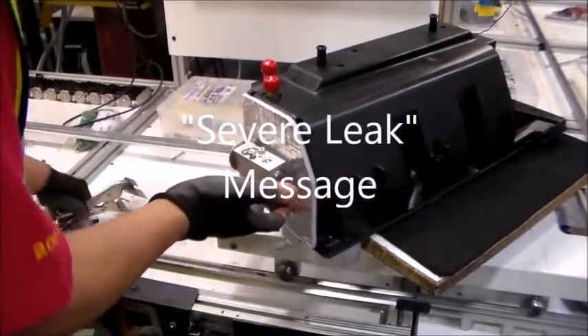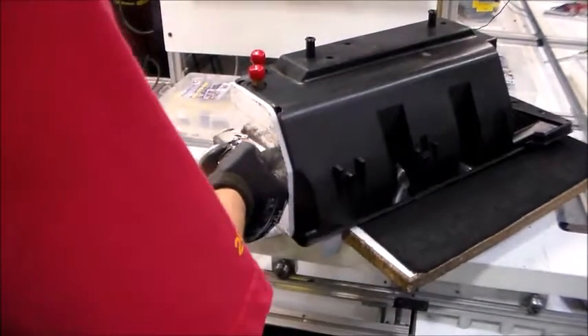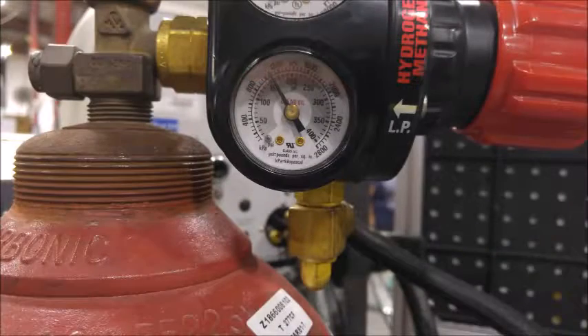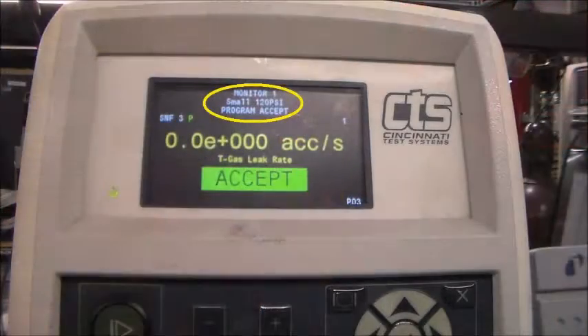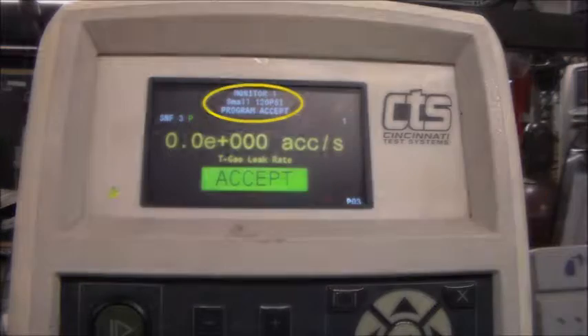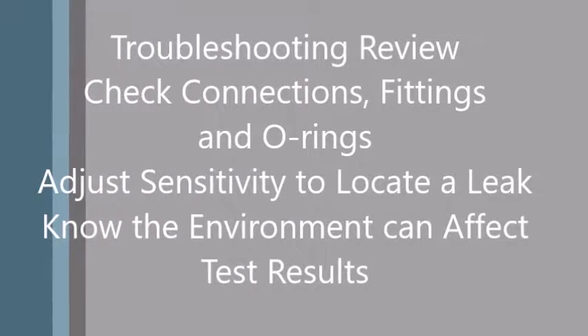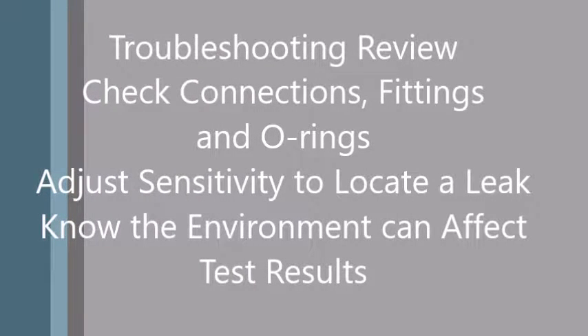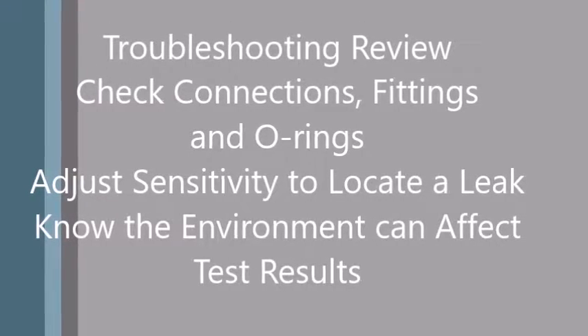If you see a severe leak message, check the fittings and part for any large, noticeable leaks. Ensure the gas is turned on and the tank is not empty, and verify the pressure regulator is set to the proper pressure for that test, and you will be all set. Overall, to troubleshoot a leak, check for any loose connections, fittings, or damaged O-rings. Know that you can adjust the sensitivity to locate a leak, and be aware that the environment you are testing in can affect the test results.